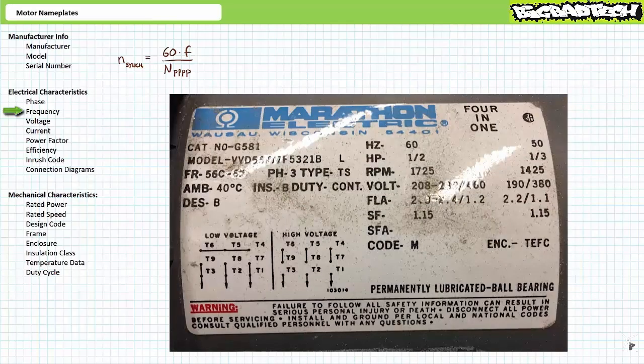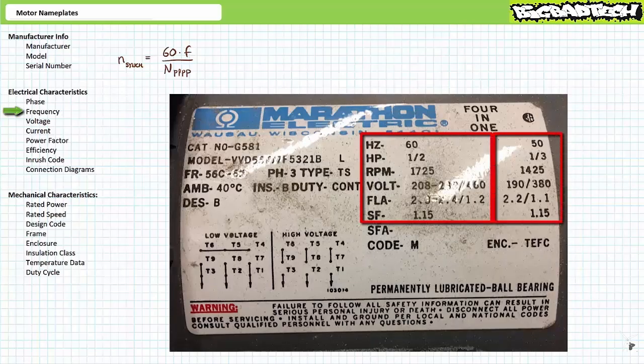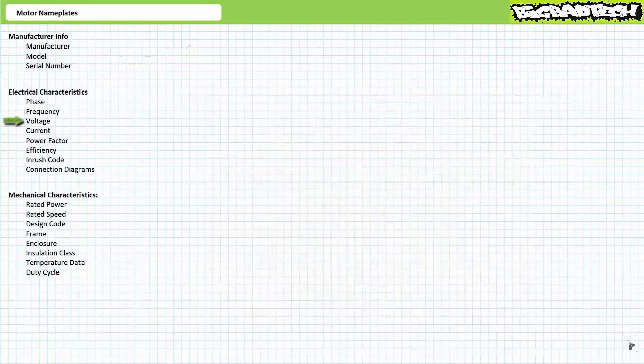Here's an example of one such motor. This nameplate has a column specifying properties at 60 Hz and again at 50 Hz. As one might expect, the rotational speed at 60 Hz is faster than when operated at 50 Hz. Voltage. This entry specifies at what voltage the motor is intended to operate, allowing for a 10% tolerance. For three-phase AC motors, this is the larger line-to-line voltage, and it is not the smaller line-to-neutral voltage.